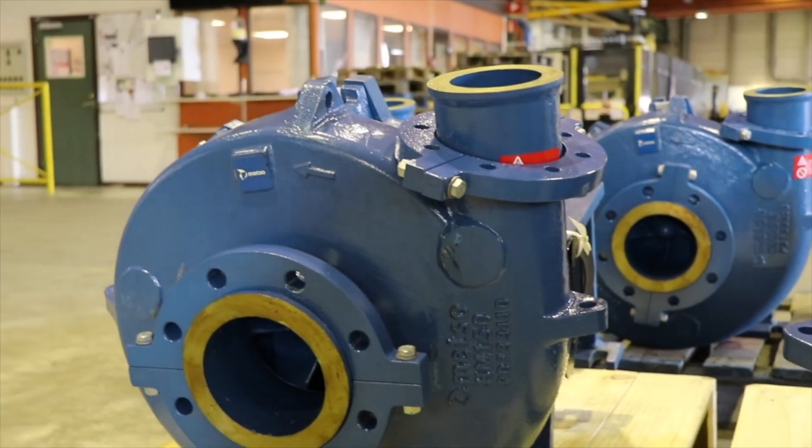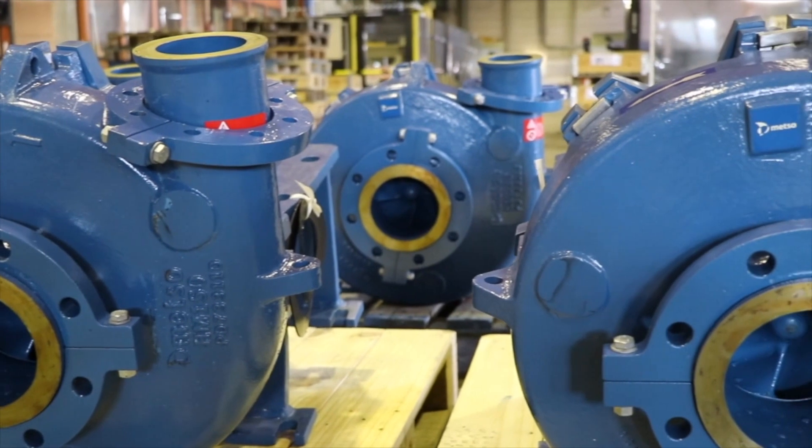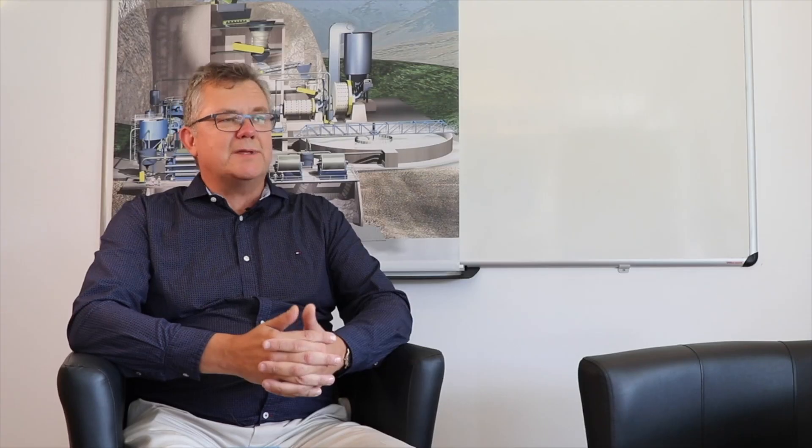In my opinion it's an overlooked potential for big cost savings and optimization. For instance, a poorly operated slurry pump may easily lose 10% efficiency just from operating away from its best operating point, and considering that 50% of the average slurry pump's cost of operation is power, it's really key to optimize. It's a quick payback to look through and optimize your slurry handling system.